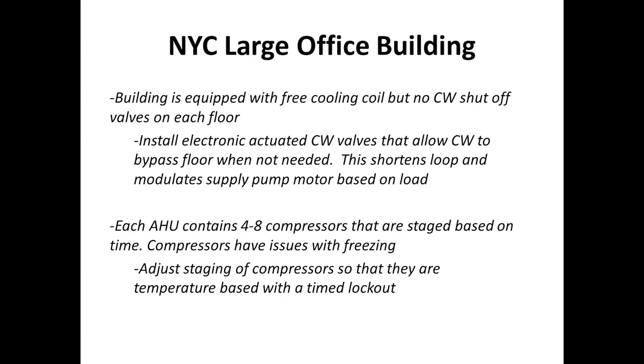Again, this building had an air handling unit on each floor. Depending on the size of the floor and the use of the floor, there were 4 to 8 compressors on each floor that were operated by the control system using control logic to stage the compressors based on a timer. So if a floor required cooling, the first compressor would kick on for a minute, and then the second compressor would kick on, the third, the fourth, all the way up until the cooling condition was met in the building.